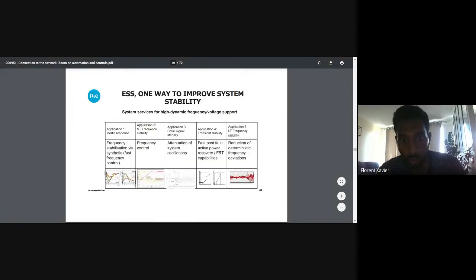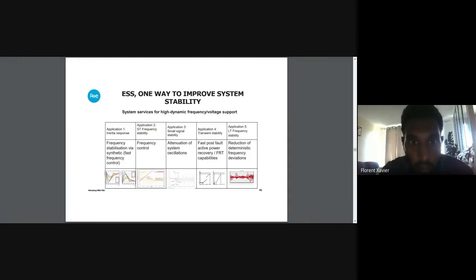So, go to this slide. The ESS are one way to improve system stability. The first is the inertia response, thanks to the fast frequency control, for example. The second is the classical frequency control, the primary frequency control. The third application is the attenuation of system oscillation. And there are other utilities, like transient stability: ESS can participate during faults by providing negative reactive power current in order to maintain voltage at a certain level and avoid collapse.